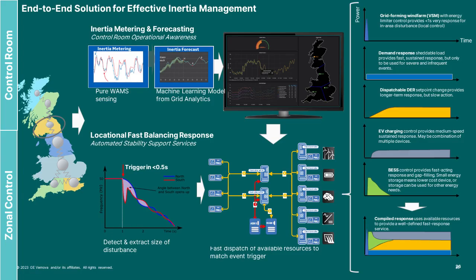As I said, the inertia monitoring uses WAMS data to measure inertia in each one of the regions, uses AI/ML to forecast, and then the WAMS controller allows us to then implement the control scheme, locational fast balancing, to help in the event that there's a disturbance to stabilize the grid using fast acting resources where they're available.